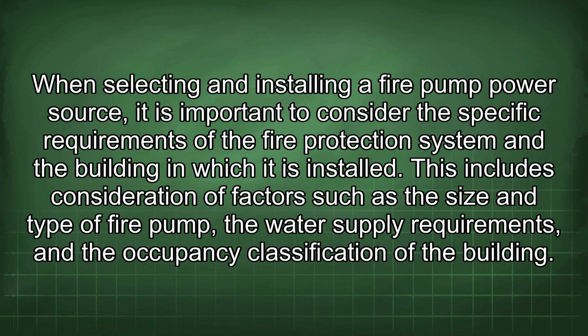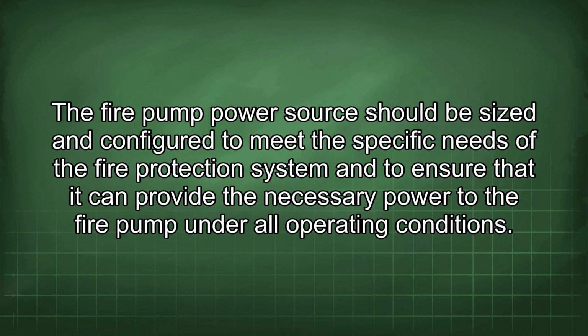When selecting and installing a fire pump power source, it is important to consider the specific requirements of the fire protection system and the building in which it is installed. This includes consideration of factors such as the size and type of fire pump, the water supply requirements, and the occupancy classification of the building. The fire pump power source should be sized and configured to meet the specific needs of the fire protection system and to ensure that it can provide the necessary power to the fire pump under all operating conditions.